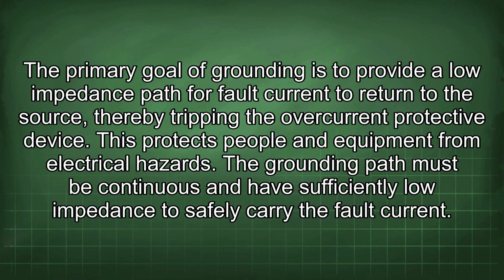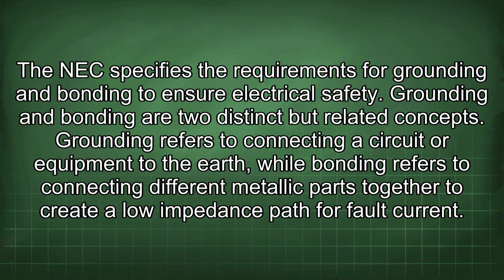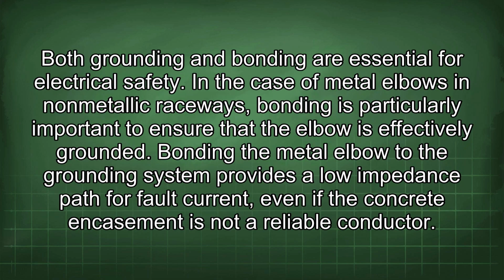The grounding path must be continuous and have sufficiently low impedance to safely carry the fault current. The NEC specifies the requirements for grounding and bonding to ensure electrical safety. Grounding and bonding are two distinct but related concepts. Grounding refers to connecting a circuit or equipment to the earth, while bonding refers to connecting different metallic parts together to create a low impedance path for fault current. Both grounding and bonding are essential for electrical safety. In the case of metal elbows in non-metallic raceways, bonding is particularly important to ensure that the elbow is effectively grounded. Bonding the metal elbow to the grounding system provides a low impedance path for fault current, even if the concrete encasement is not a reliable conductor.